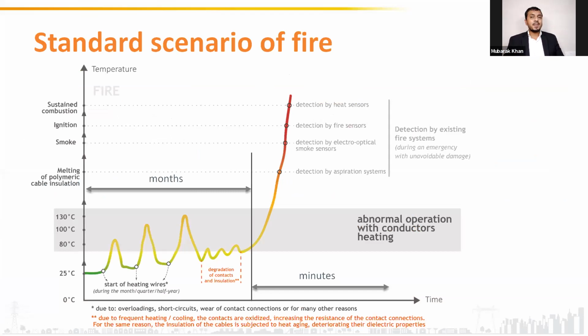Okay, standard fire scenario. In this example, we have taken how a loose connection can convert into a fire. And for simplicity and for explaining it better, we have taken a scenario where the connection is not very loose, but rather insufficiently tightened. Under this scenario, when the joint is under normal conditions, it will not have any abnormality and will run normally. The temperature of the joint under normal condition will be between 25 to 70 degrees Celsius, depending on the ambient temperature. When there is a small abnormality, maybe in case of full load or overload, the temperature of the joint will increase. Let us assume it reached 80 degrees Celsius because of the overload. When the load clears, the joint temperature will come down again. But when it comes down, it will not come down to the original point, but rather to a little higher value, and it will remain there.